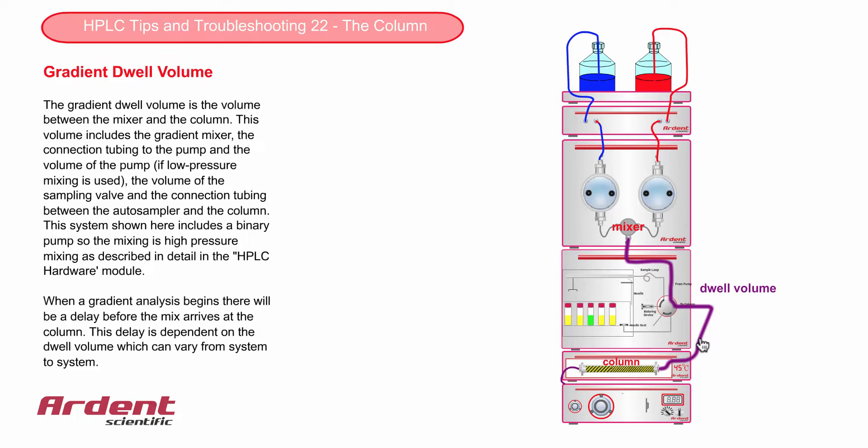There will always be a dwell volume, but it is much reduced when using a binary pump. This is because the mixer is always on the high pressure side of the pump, and so the dwell volume does not include the volume of the pump itself, which could be up to 1 mL.